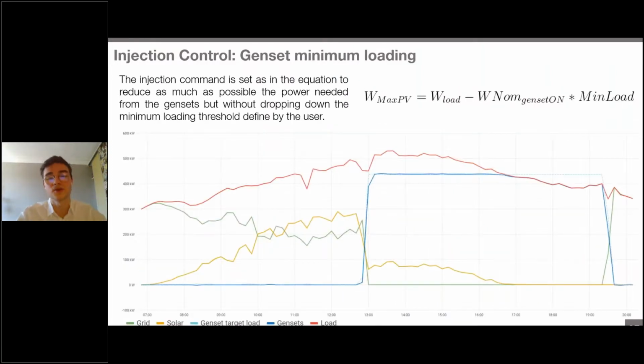Here is another example of the e-power control managing a system. This is a backup application for a weak grid, and in blue you have the genset power. Around 1 o'clock, there was a grid outage, so the gensets were turned on to ensure we still had energy flow to the load.